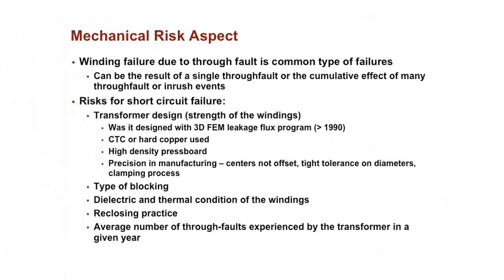Now, in the past they would use low-density press board, and over time that would become loose. So that's one type of blocking we look for, and we don't like that. If they used high-density press board, that was better. There are some designs with what they call dash pots. It's almost like a spring that follows the windings, and this keeps the pressure on the windings. So that was a very good clamping process. These are the types of things that are taken into account when you're looking at the transformer design.